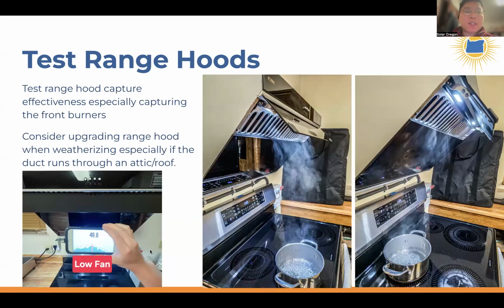But sometimes it's not the ducting, sometimes it's the range hood, and some range hoods just really suck at capturing cooking emissions. And so, if you have a range hood that runs through an attic, especially if you're going to do attic weatherization, replace that range hood beforehand, because sometimes the range hood that you want, that has very good capture efficiency, needs a different diameter duct, and so then you're in the attic cutting the hole bigger and replacing that ducting to be the correct size. In order to have a very quiet range hood, you generally need a pretty good sized duct, like a 7 or 8 inch duct, in order to have low enough static pressure to allow the range hood to flow air effectively while staying quiet.